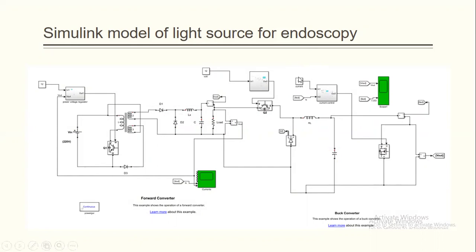Similar to before, we have a desired input current. Here it's 40 and the closed loop from the current measurement sensor. And the error between them will be calculated and will be as an input to the PID controller that plays a role in specifying the duty cycle.